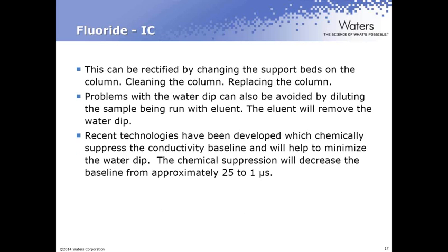Problems with that water dip can also be avoided by diluting the sample being run with eluent. Because what happens there is if you dilute it with the eluent that you're running on your instrument, it removes the water from the sample and will essentially remove that water dip.